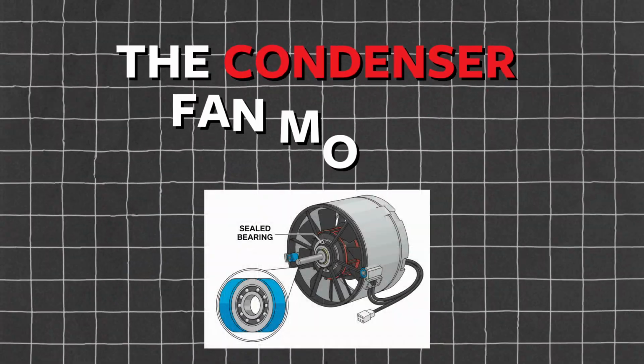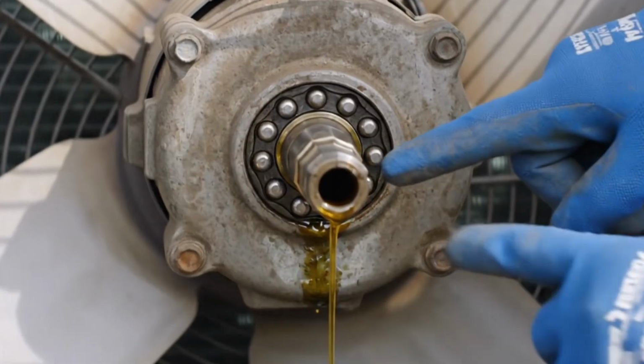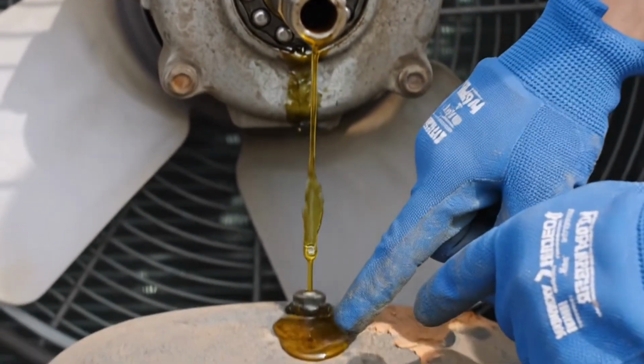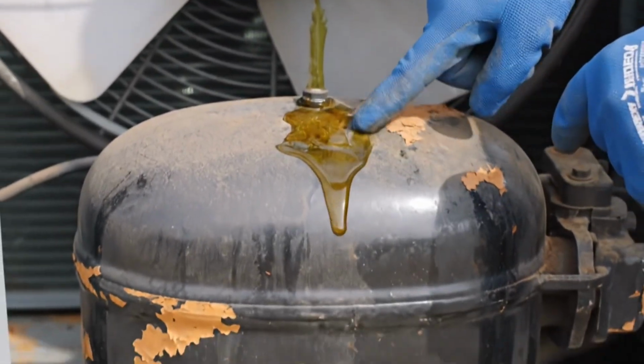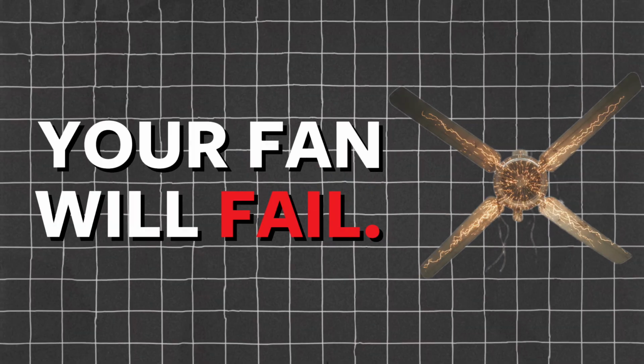One, the condenser fan motor has sealed bearings. Those bearings will eventually wear out and start to leak. One of the signs you want to look for as your bearings wearing out is oil on top of your compressor. If you see oil on top of your compressor, here's what I can guarantee. Your fan will fail. I just can't tell you when.